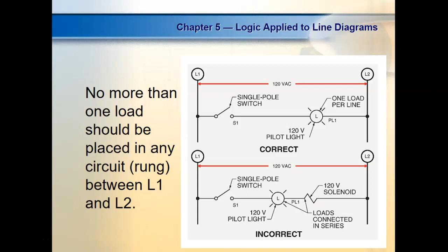Because if we take a look at this previous one right here, this looks like the light should be directly connected to the solenoid. We don't really want to do that, because the light has to have its own set of voltage, and that solenoid has to have its own set of voltage, or else the two don't work. So if you take that versus this, both of these are running 120.